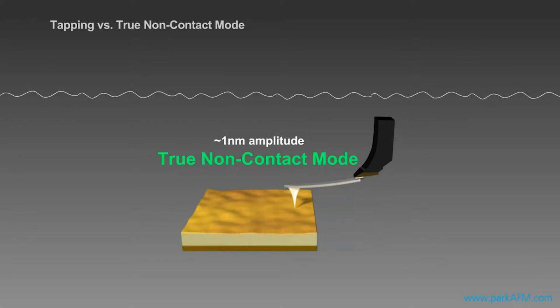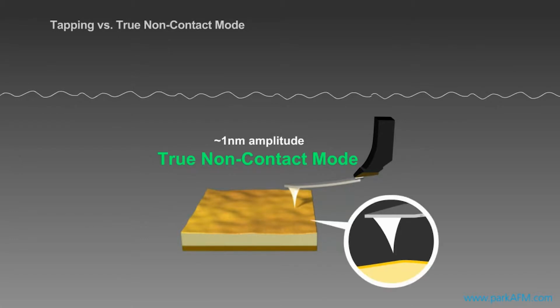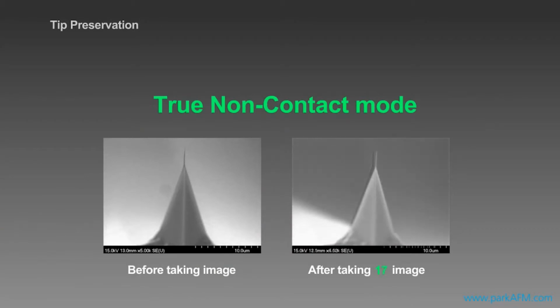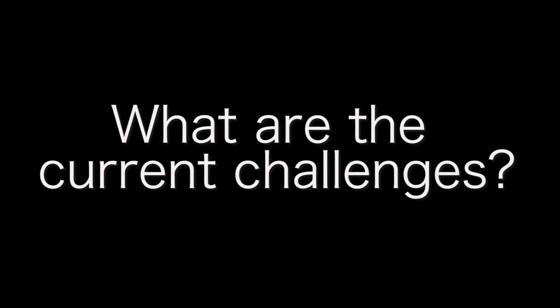So that's why we needed to develop non-contact mode. In order to make a non-contact mode, if we operate like tapping mode, then it gets trapped at the bottom. So we had to raise the cantilever much higher, give low energy, and move much faster with the servo, and doing it this way we achieve non-contact mode.